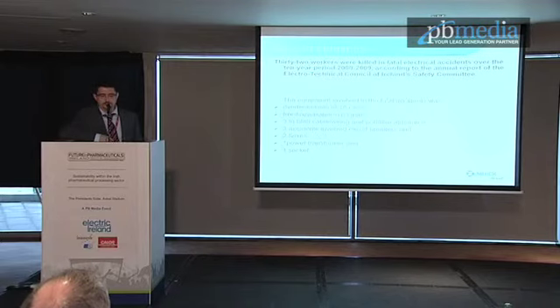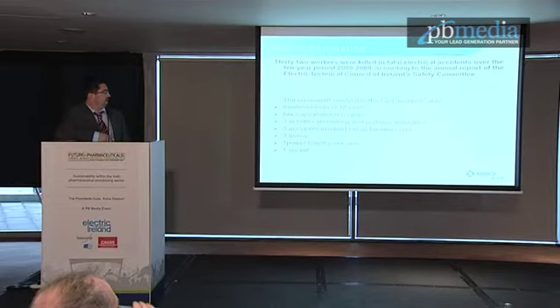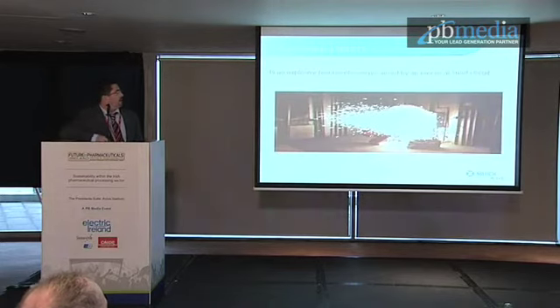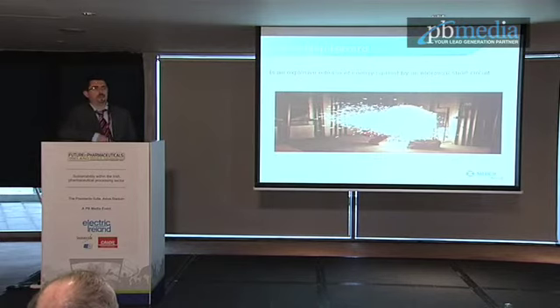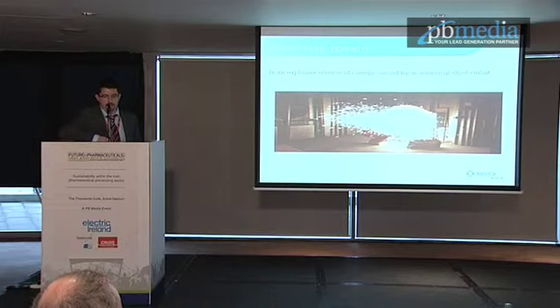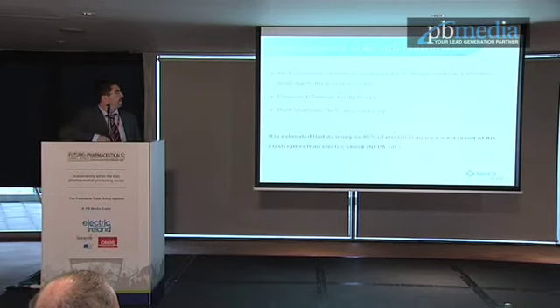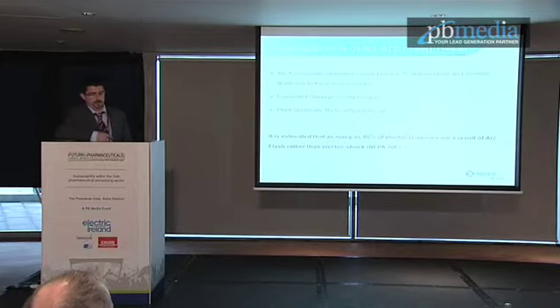So here are some statistics. Over 32 workers were killed in fatal incidents in the period 2000 to 2009. These range across different cases in an electrical distribution system, from overhead lines to fixed apparatus, cable wiring systems, power transformers, etc. One of the most serious risks associated with any electrical system is the electrical arc flash. What is an arc flash? It's an explosive release of energy caused by an electrical short circuit. Arc flash injuries range from minor burns to third degree burns, equipment damage and plant shutdown, and it's estimated that as many as 80% of electrical injuries are a result of arc flash rather than electric shock.